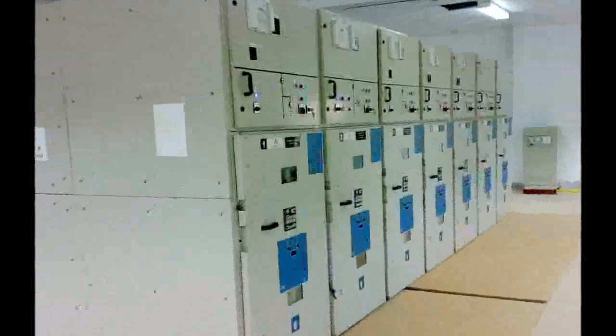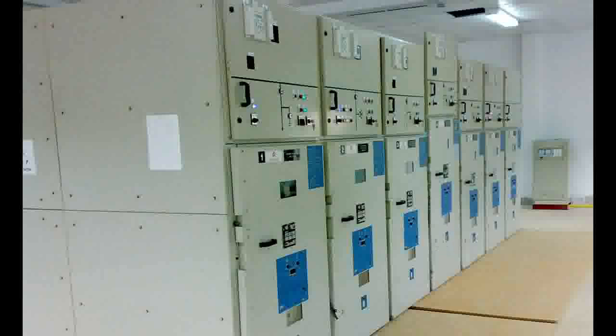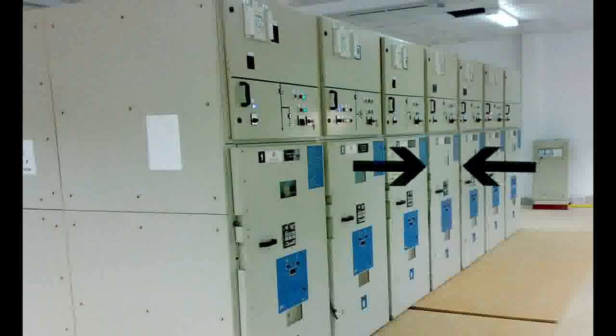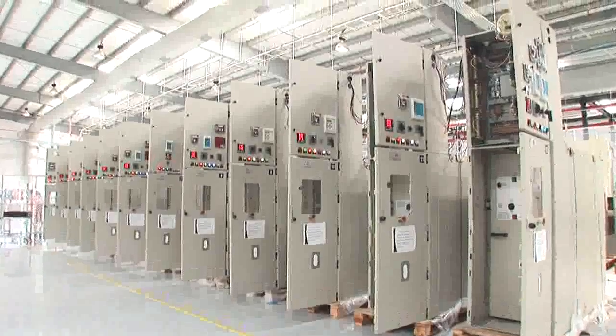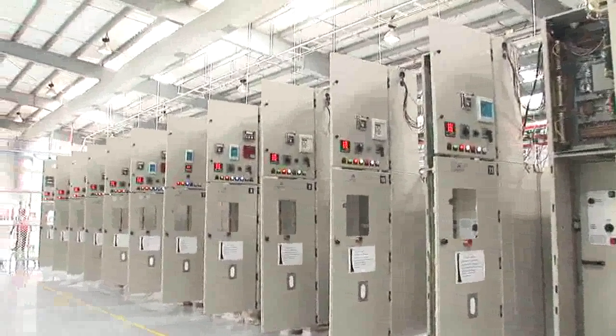Another weakness of the old IEC requirement was that it did not specify as to which cubicle should be tested for the internal arc test. This implied that the choice of cubicle was left to the manufacturers. The manufacturer always tested the middle cubicle of a switchboard, claiming to simulate the real-life working condition. However, this method of testing actually protected the enclosure by providing support to it from the two sides. All it had to do was to withstand the pressure on the front door and the rear cover. The side walls were automatically protected by the side cubicles.